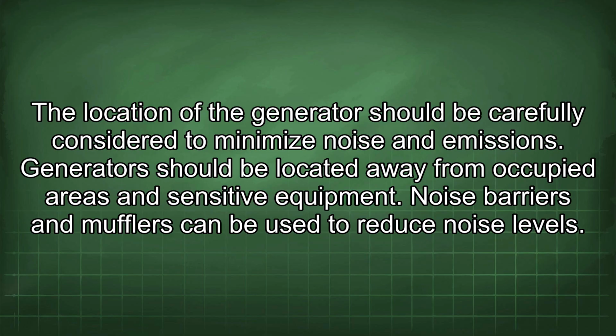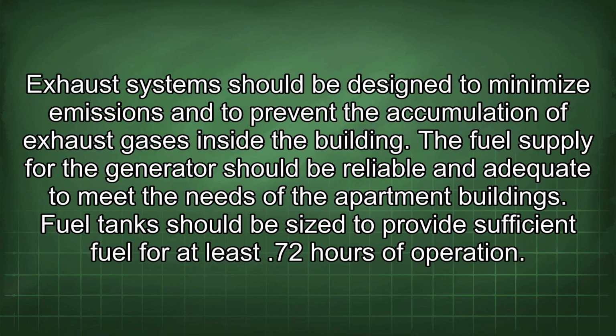The location of the generator should be carefully considered to minimize noise and emissions. Generators should be located away from occupied areas and sensitive equipment. Noise barriers and mufflers can be used to reduce noise levels. Exhaust systems should be designed to minimize emissions and to prevent the accumulation of exhaust gases inside the building.